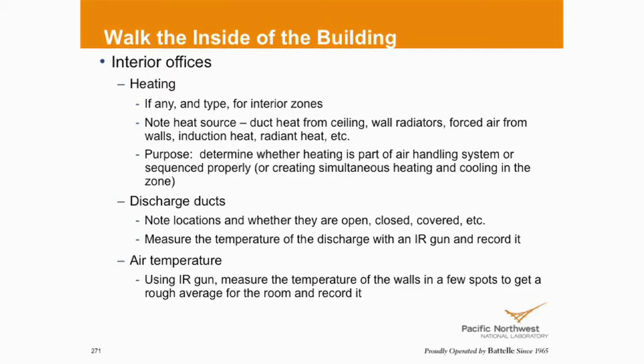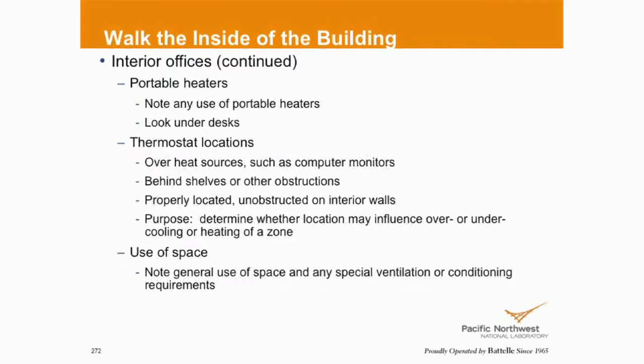Again, measuring temperatures coming out of diffusers, looking at wall temperatures, space temperatures, and so on. Portable heaters we've already talked about. Thermostat locations we've already talked about. How is the space being used? Is it an office space? Was it converted to a training space? Was it converted to a data center space? Was it being used for what the engineer originally designed or intended it to be?